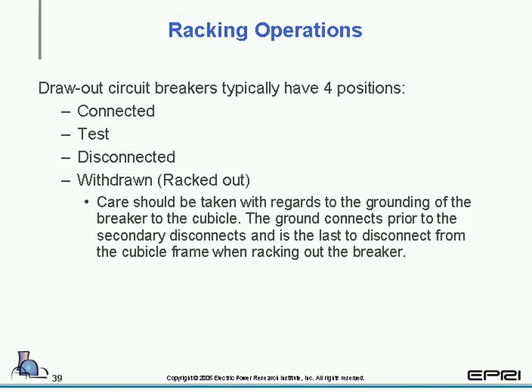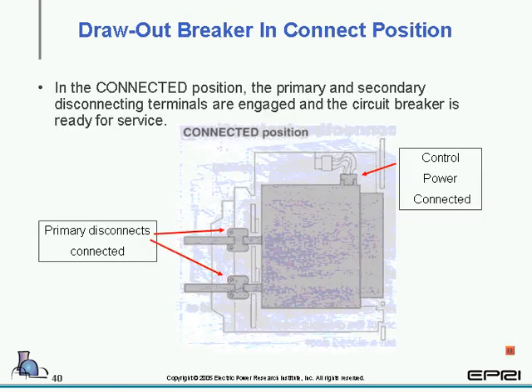Racking operations: the draw-out breakers typically have four positions: connected, test, disconnected, and withdrawn. And we also have a note to take care that the ground clip must mate even before it goes into the disconnect position or test position. And let's take a look at those a little more closely.